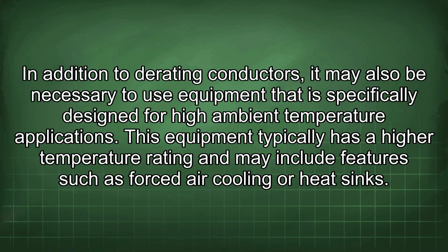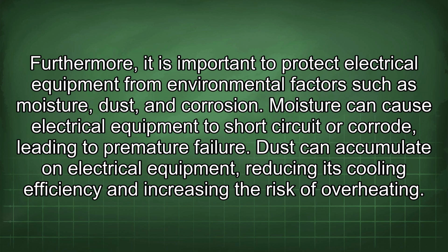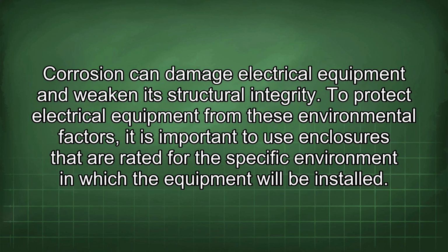In addition to derating conductors, it may also be necessary to use equipment that is specifically designed for high ambient temperature applications. This equipment typically has a higher temperature rating and may include features such as forced air cooling or heat sinks. Furthermore, it is important to protect electrical equipment from environmental factors such as moisture, dust, and corrosion. Moisture can cause electrical equipment to short-circuit or corrode, leading to premature failure. Dust can accumulate on electrical equipment, reducing its cooling efficiency and increasing the risk of overheating. Corrosion can damage electrical equipment and weaken its structural integrity.